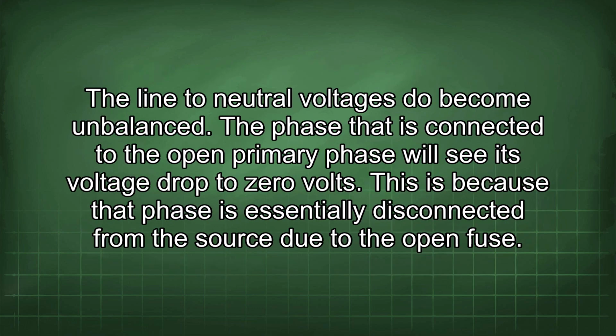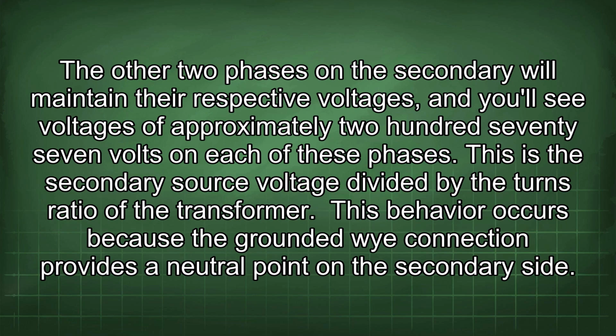The line-to-neutral voltages do become unbalanced. The phase that is connected to the open primary phase will see its voltage drop to 0 volts. This is because the phase is essentially disconnected from the source due to the open fuse. The other two phases on the secondary will maintain their respective voltages, and you'll see voltages of approximately 277 volts on each of these phases. This is the secondary source voltage divided by the turns ratio of the transformer. This behavior occurs because the grounded Y connection provides the neutral point on the secondary side.